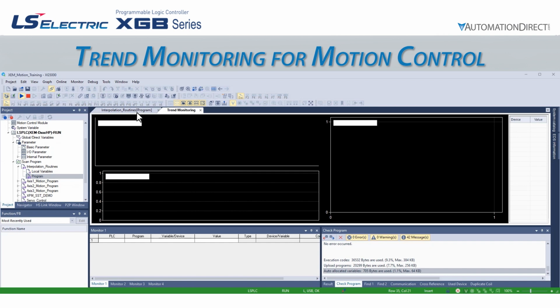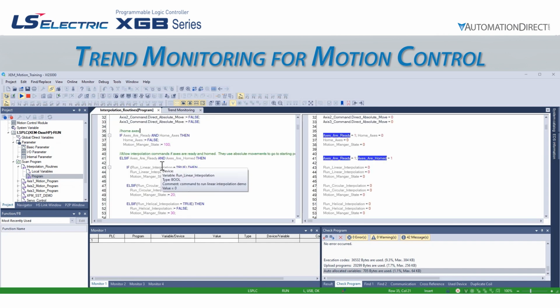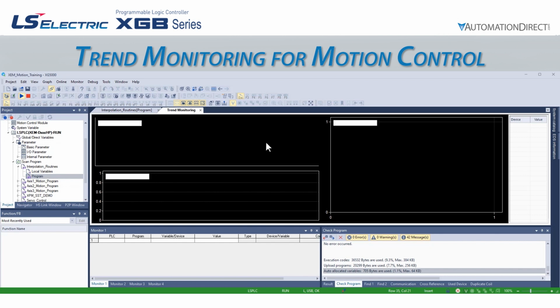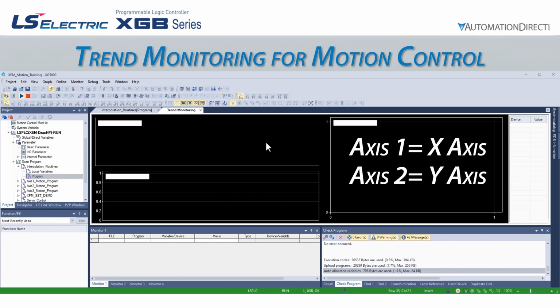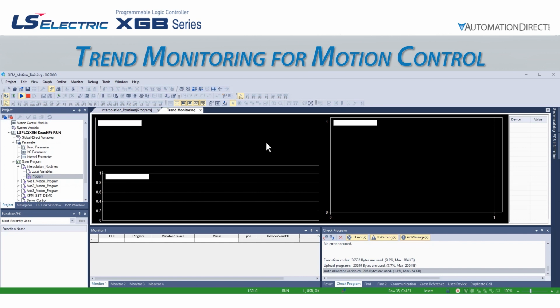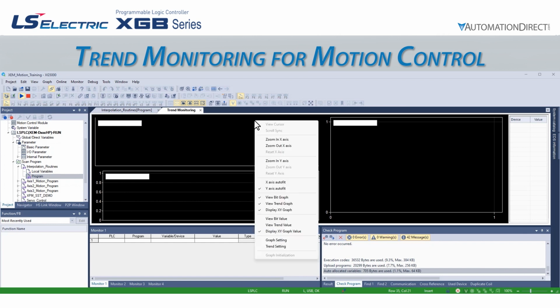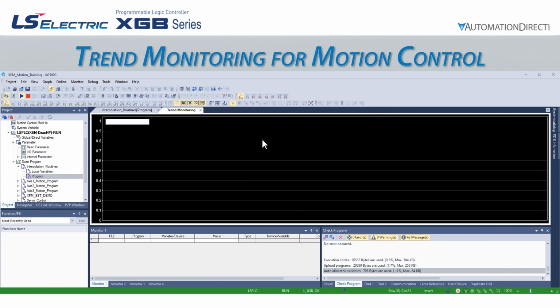Our project has several motion profiles programmed into it. We will run the circular profile and observe the X and Y position data to see our movements as they execute. First, we need to add the data we want to monitor to the graphs. Let's look at the trend graph first. Our program uses axis 1 for the x-axis and axis 2 for the y-axis. We don't need to see the other graphs, so let's right-click in the Trend Monitoring window and unselect View Bit Graph and Display XY Graph. This unselects these 2 graphs and removes them from the window.